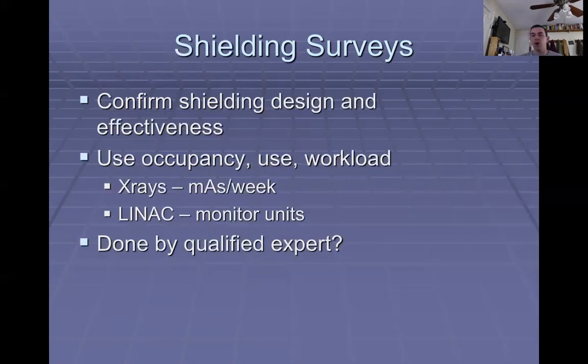For something like a LINAC vault or just a basic X-ray room, we have to confirm the shielding design and the effectiveness. It's all theoretical until it's physically built. Larry Dower, the RSO, is in charge of actually designing these facilities, and there are programs and other ways to verify that you're doing it right. You design in safety factors, but ultimately you really need to make sure that it was built correctly. You could have the best design in the world, but if it's not built correctly, it could be a hazard.